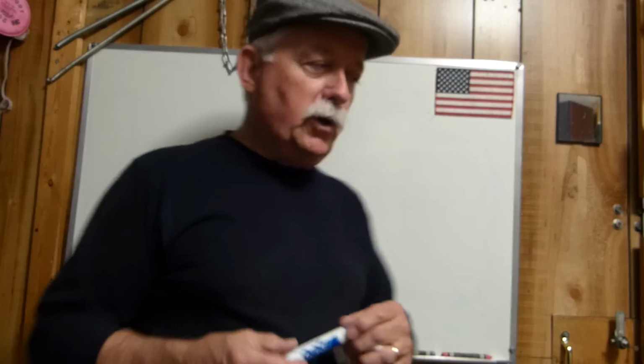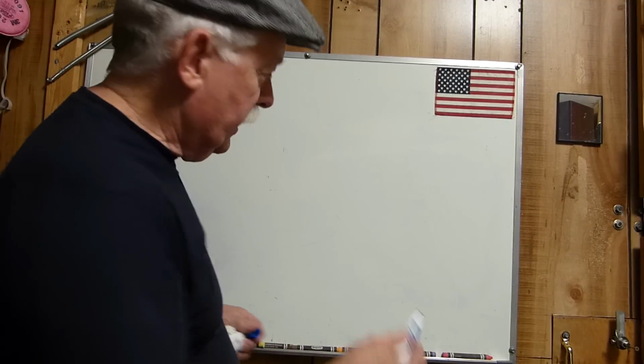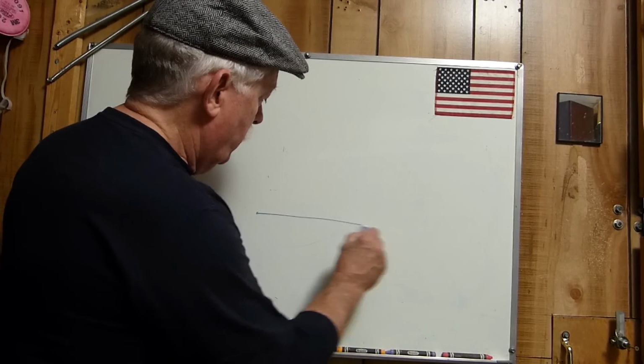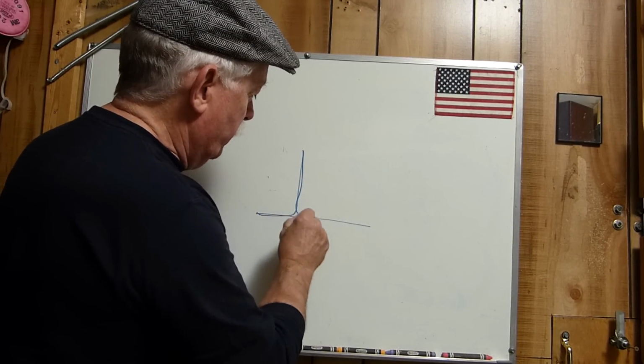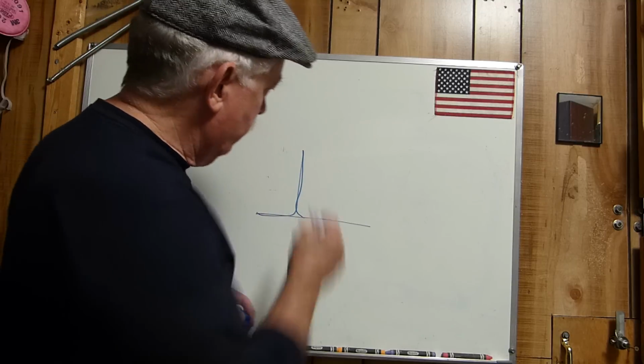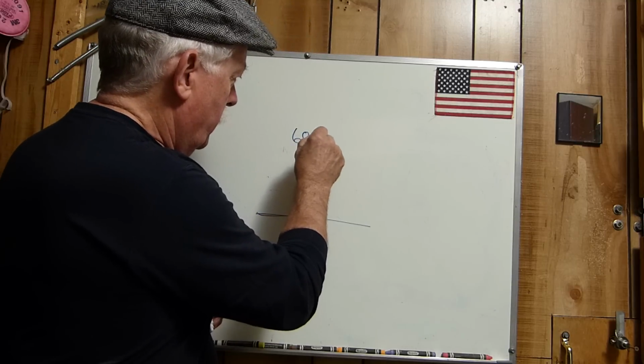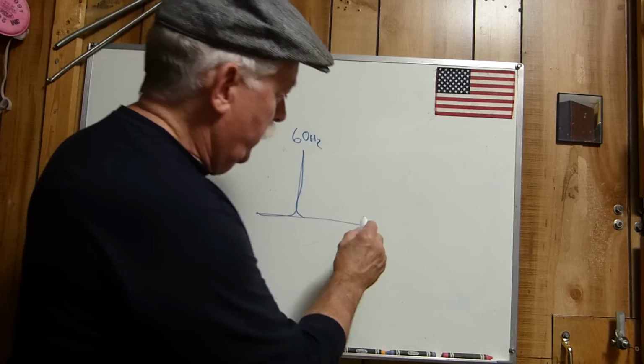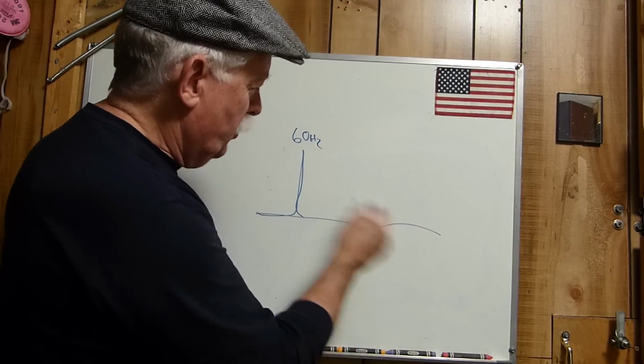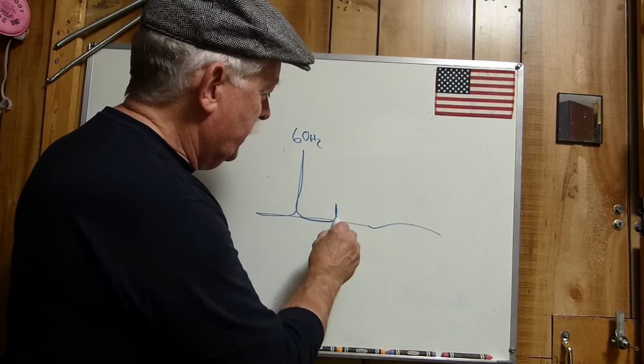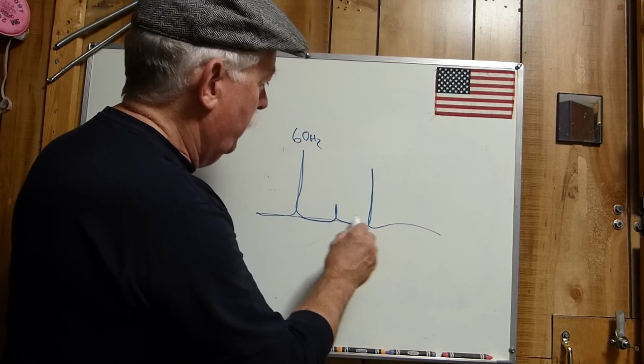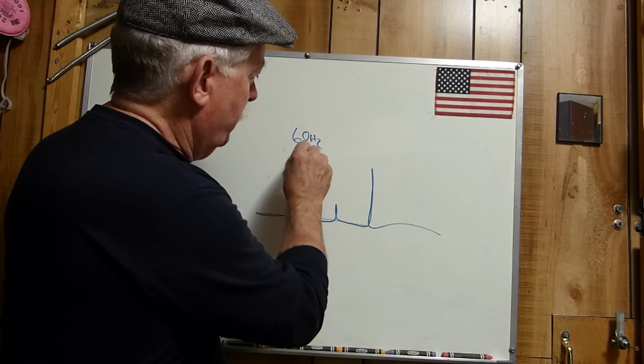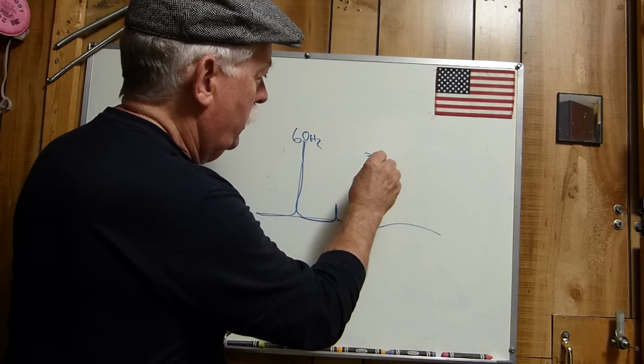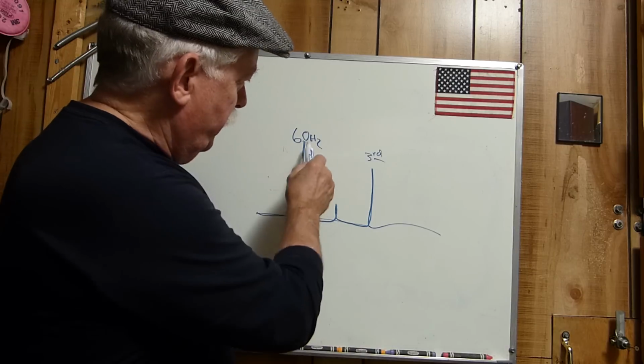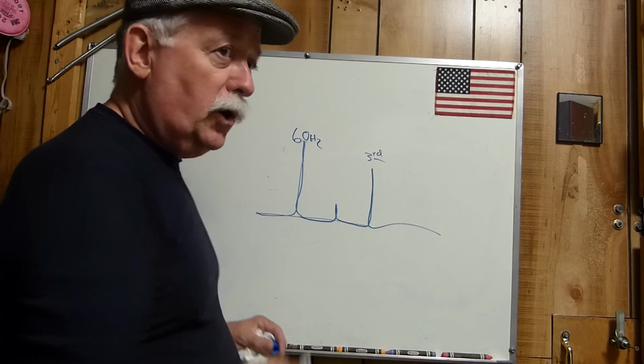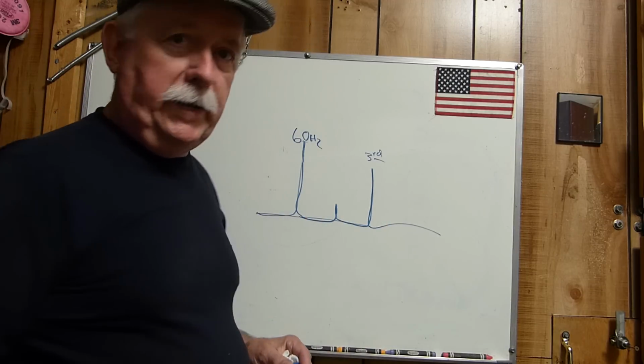What a zero sequence harmonic is: if you look at it on a spectrum analyzer, this is the fundamental frequency - let's just call it 60 hertz to keep it simple. The offending frequency gets more complicated than this, but basically you'll have a second harmonic out here, and a third harmonic out here that's really huge - not as large as the fundamental, but still a very large third harmonic.